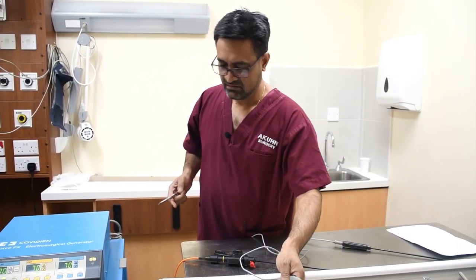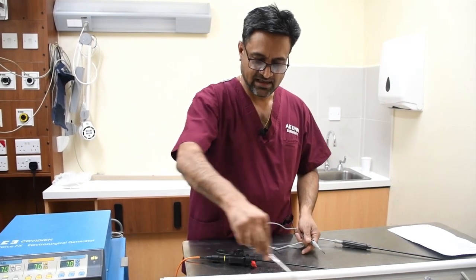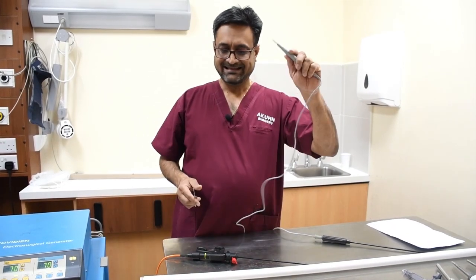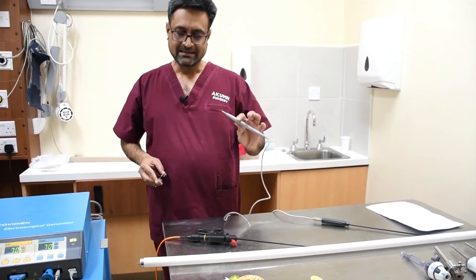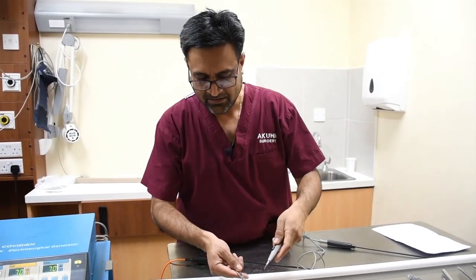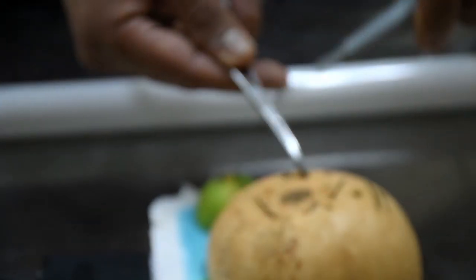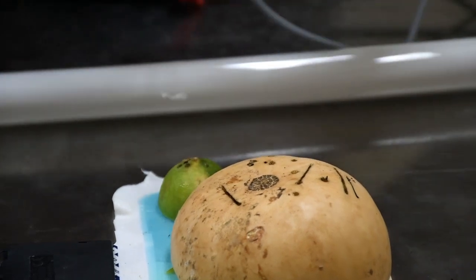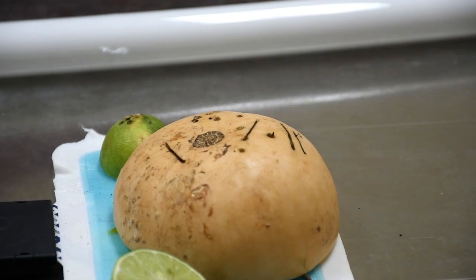Another important application is, for example, when you are doing a surgery and you have held vessels. So when you have held the vessels and you want to buzz the vessels because you want to stop the bleeders, what is the normal way we would do it? If you ask most people, they would say I would use coag to coagulate and I would use cut for something else. Well, that's wrong use of electrosurgery. That's what I was trying to tell you. The correct way of electrosurgical use would be to use the yellow as a hemostat. So you've held a vessel and then you would use the yellow and activate. What difference does it make? When you're using the blue, it is very high voltage, so it's very dangerous, as we have discussed. So what will happen here? There will be many of you who would say, maybe by a show of hands we can check, who would say that when they were operating once and they were buzzing vessels like that, they suddenly got a shock or a burn.